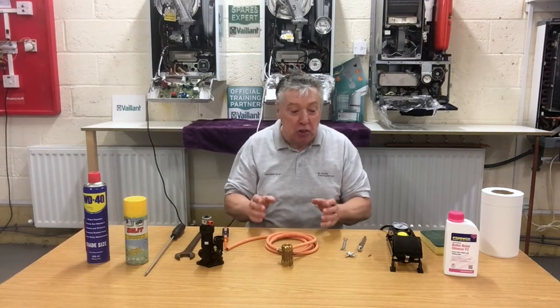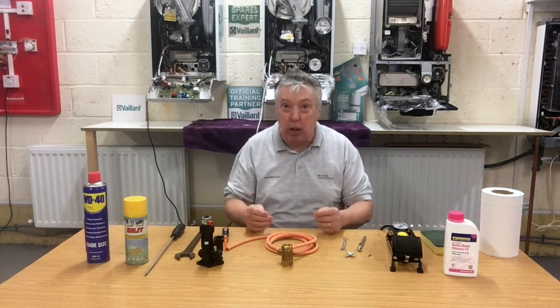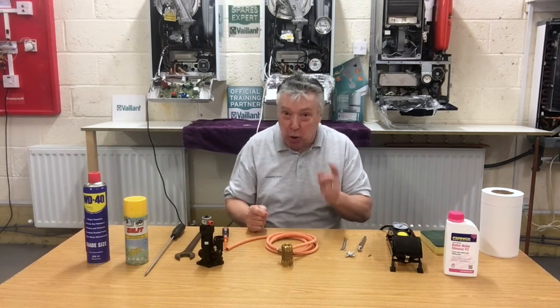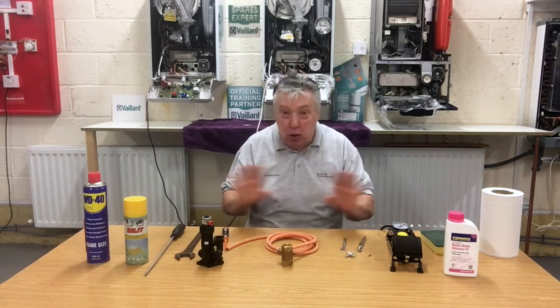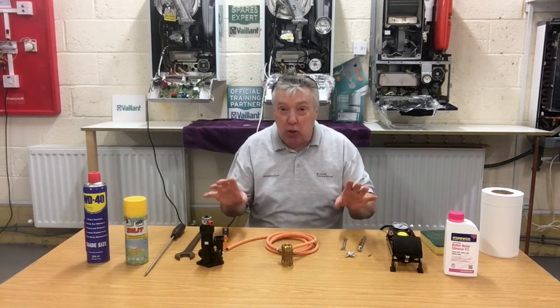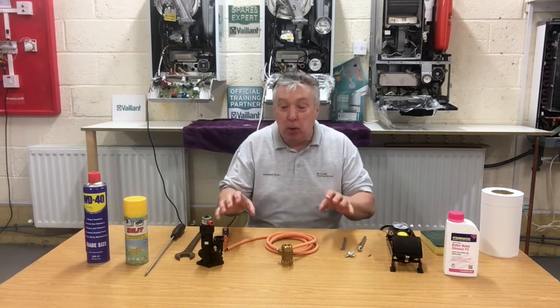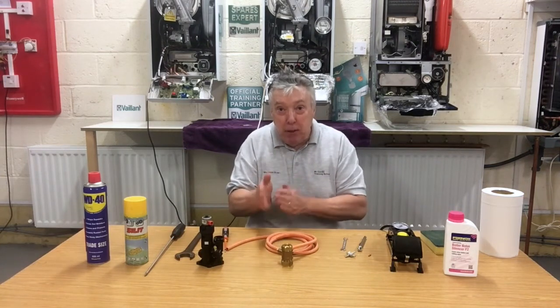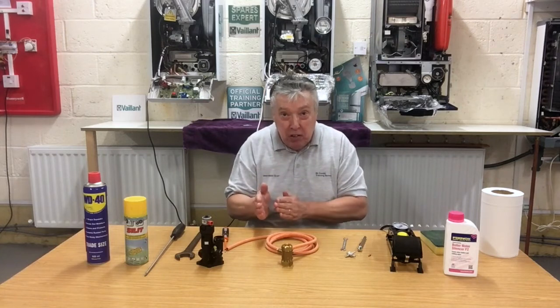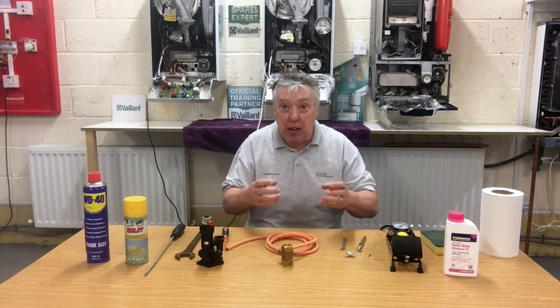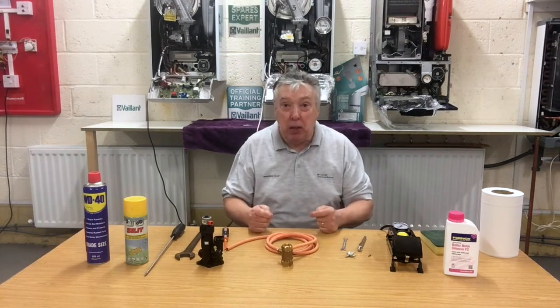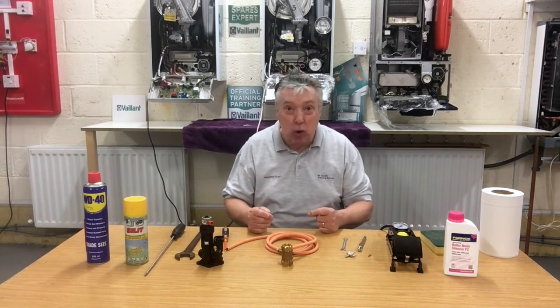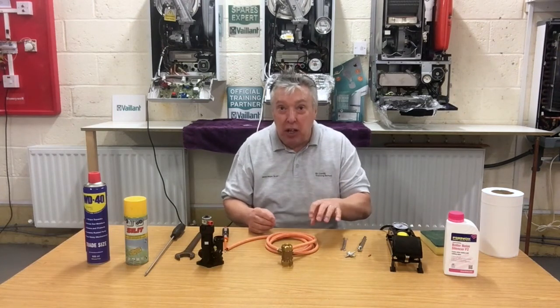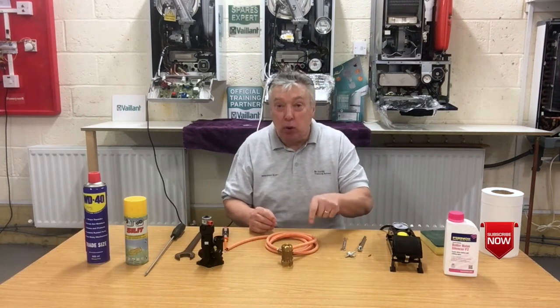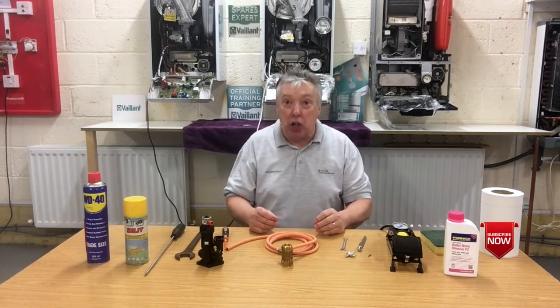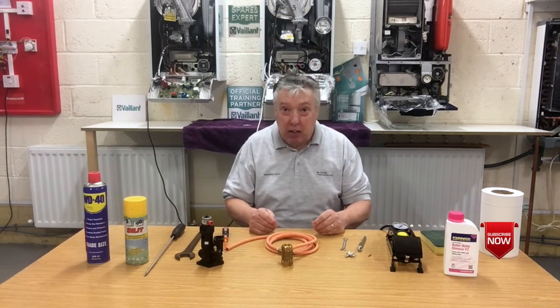The procedure will be to put the boiler into the P program, which I'll show you in a minute, because that's absolutely compulsory. Whenever you drain down the boiler, you must put the diverter valve in the mid position, which is P6, and then when we fill and vent, we go into P0. Do not do anything else unless you've read the installation manual for the boiler you're working on about draining down, filling and venting.